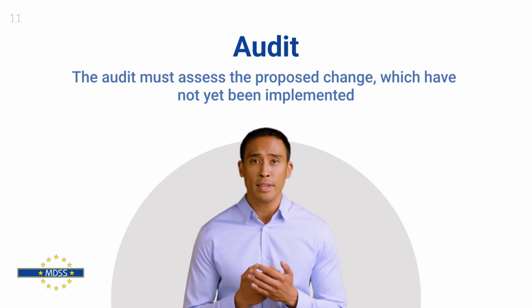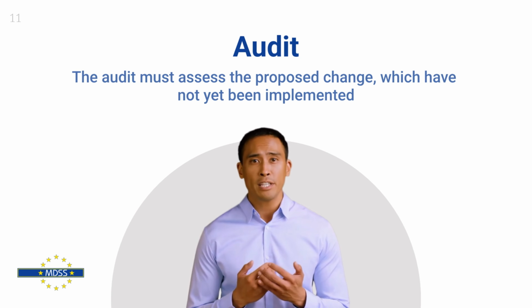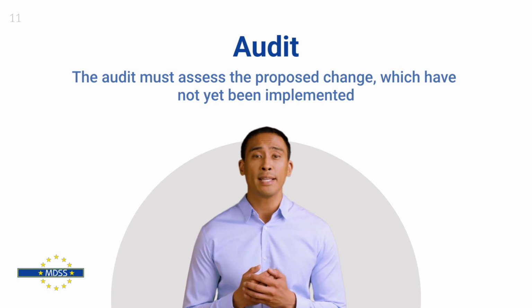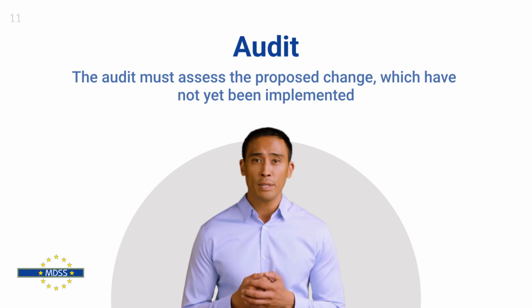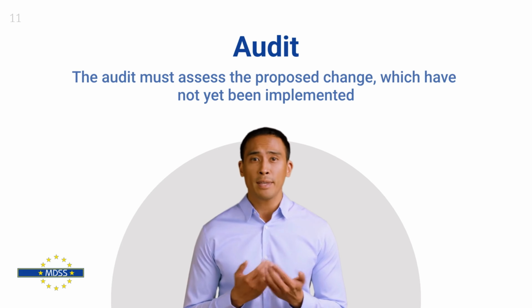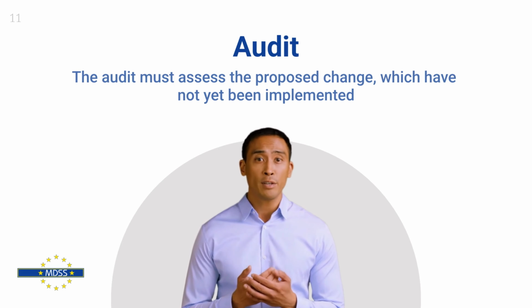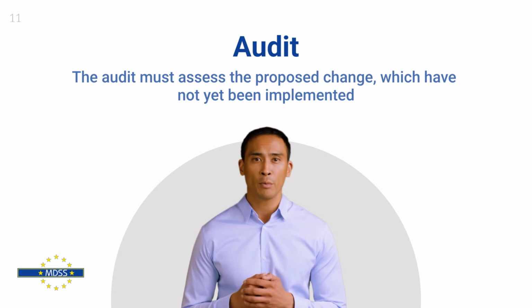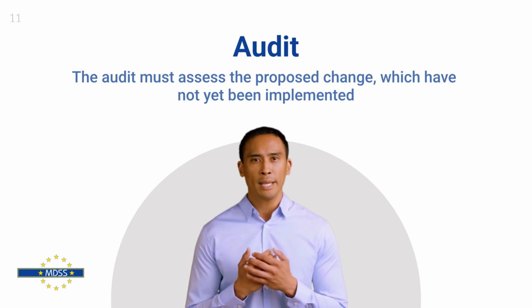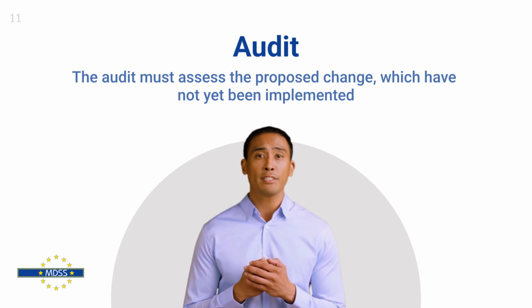It's a forward-looking evaluation. The notified body is checking whether the quality management system, as it will be after the change, will still comply. Only after the notified body is satisfied through its review and audit, if required, can it issue the supplement, which is the formal approval. Only then may the manufacturer implement the change.